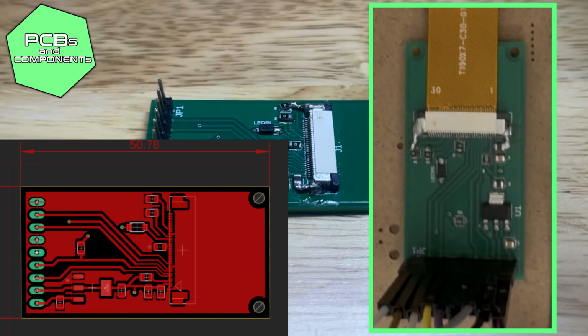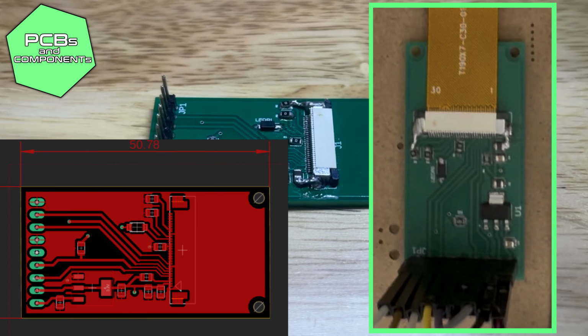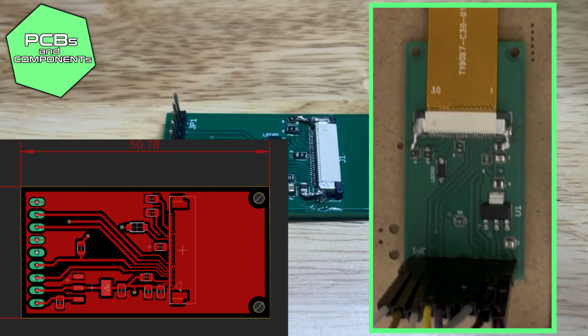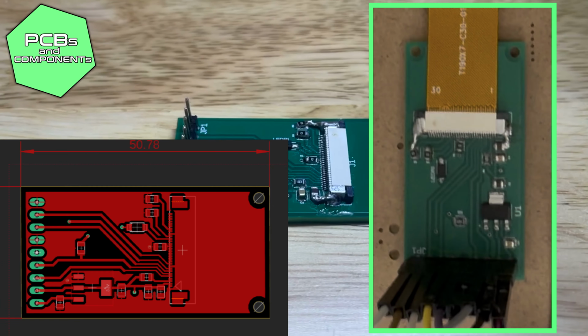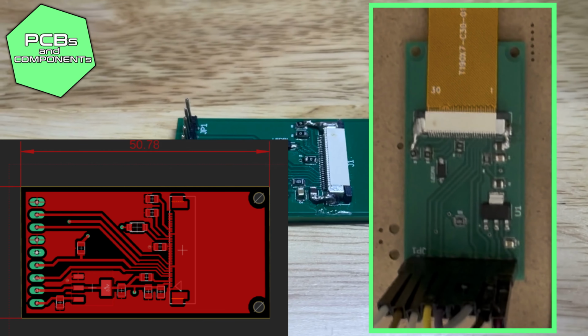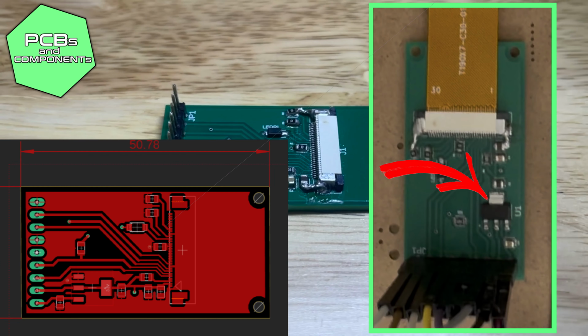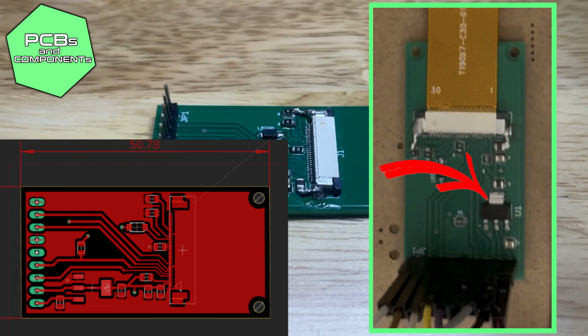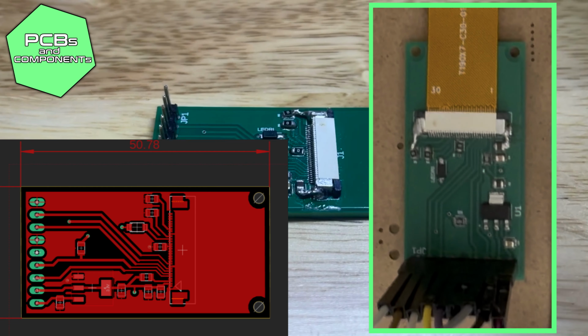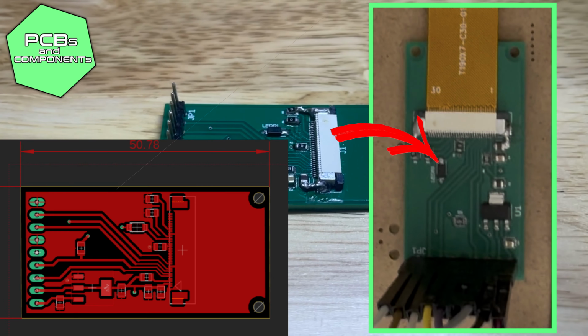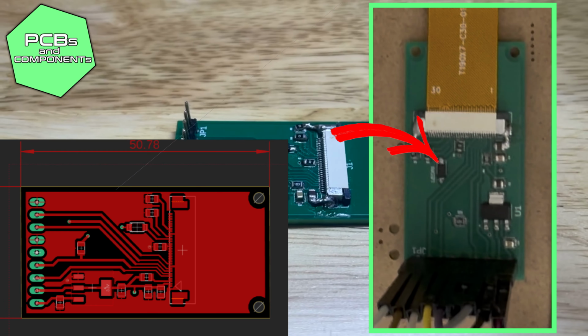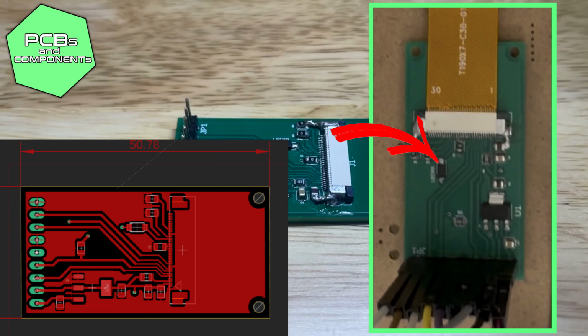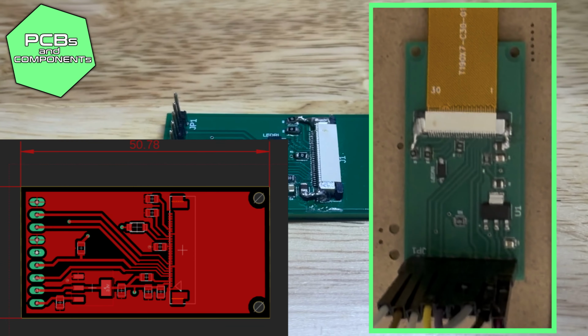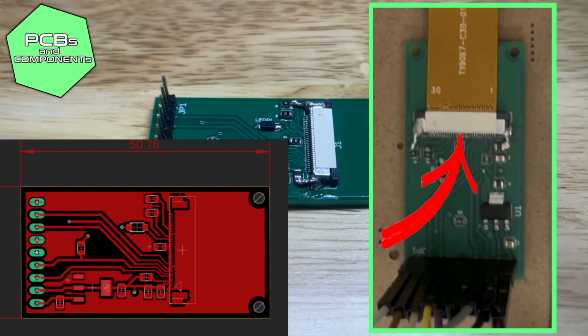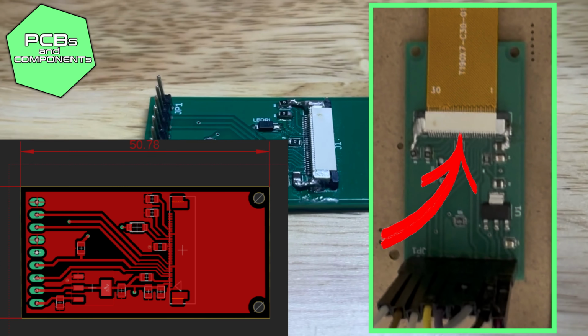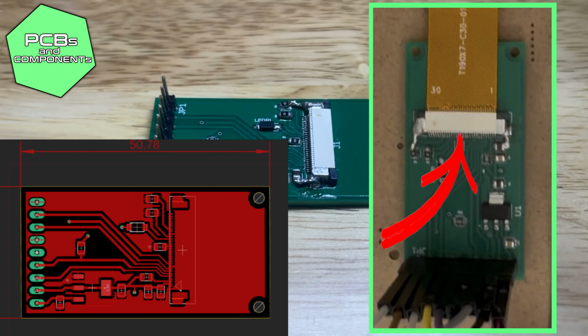This PCB is the main driver for the LCD display located on the front of the breaker. It utilizes the SPI protocol to communicate with the ST7789 TFT driver embedded with the LCD display itself. As can be seen, there is a linear regulator on board to drop the 5-volt signal down to the appropriate logic level of 3.3 volts for use with the display. In addition, the backlight is powered through a 60 mA constant current driver, which as the name implies, outputs a constant 60 mA to the backlight so long as the 3.3 volt regulator supplies it. All of the respective signals here are connected to the 30-pin ribbon connector, which is what the LCD itself slots into to be able to take the communication signal present on the driver PCB.